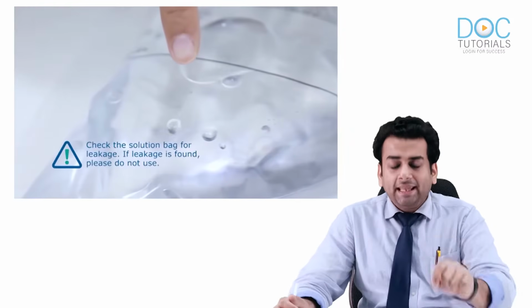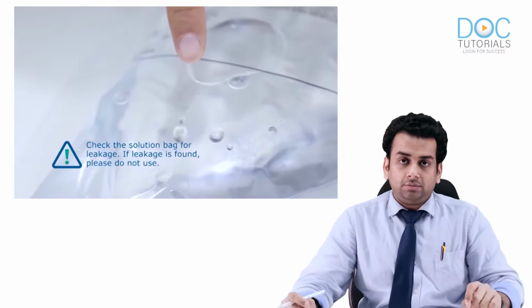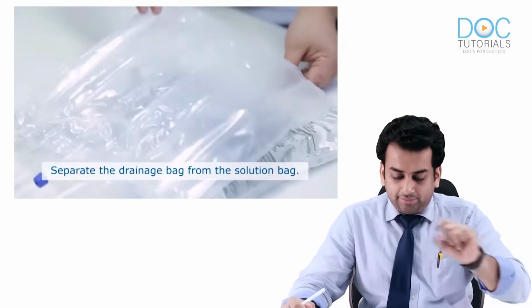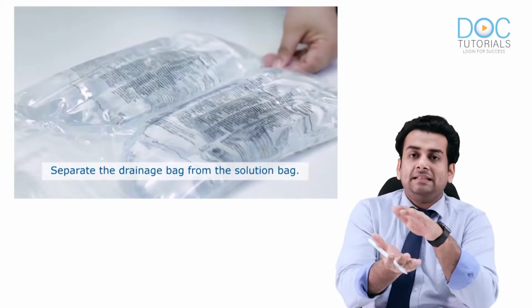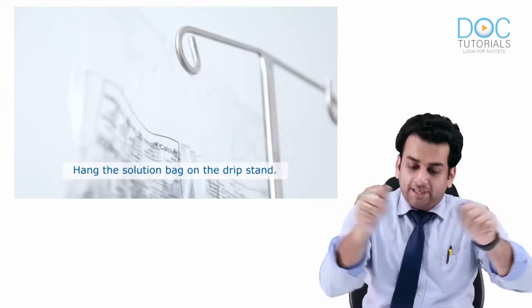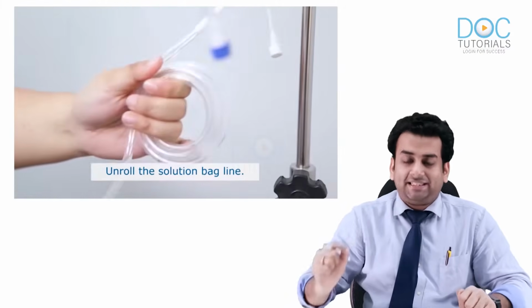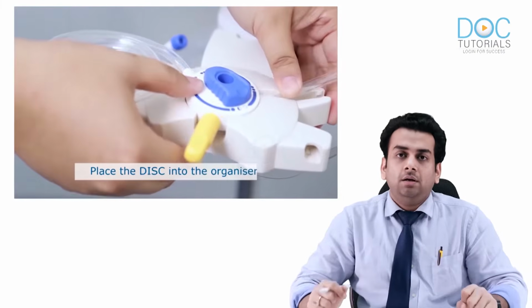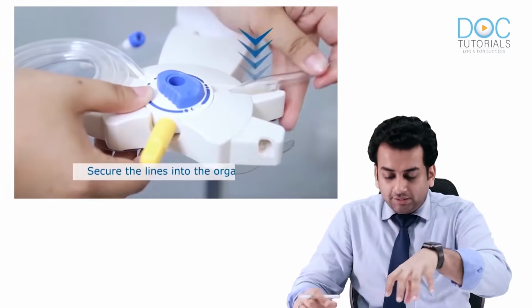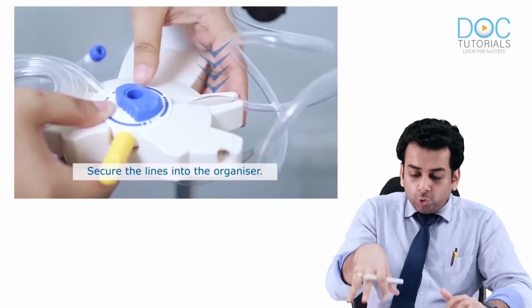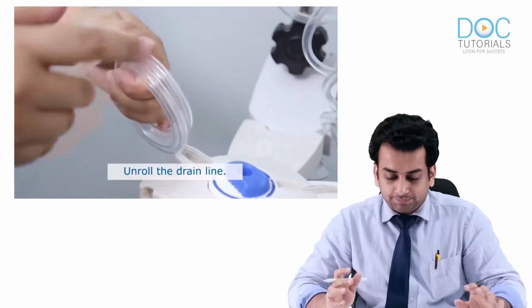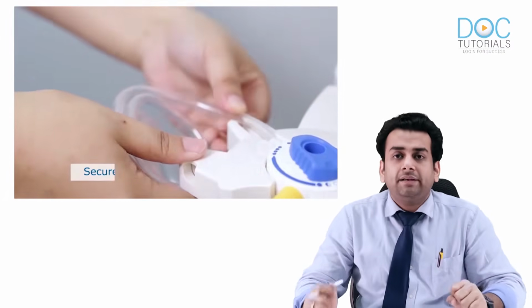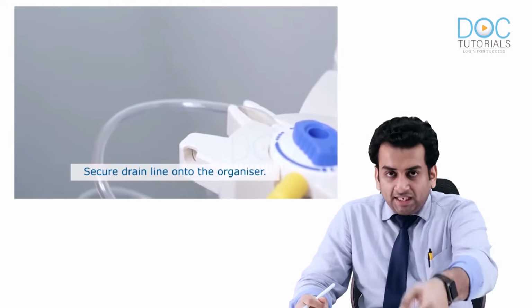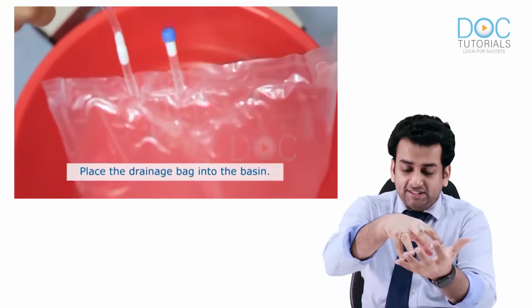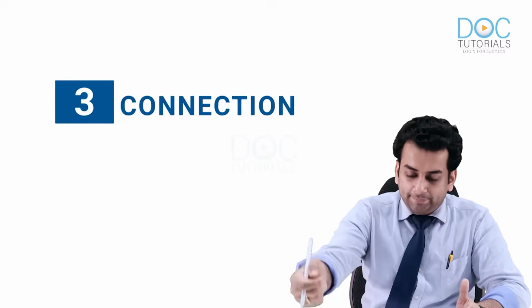Then you again check for any leaks outside. There must not be any leak anywhere. Then you will find that the PD bag and a drain bag are very closely stuck to each other. You separate both of them and you hang the PD bag with a stand and you straighten the tubing attached to it. Then you attach the Y portion attached to the bag, to the tubing, to the organizer disc that you already possess. Then you straighten the portion of the drain bag. Now, you will secure the line into the organizer. Now, the best part is it is so designed that you cannot afford to make a mistake. It will only fit in one direction. You put the drain bag into a basin.